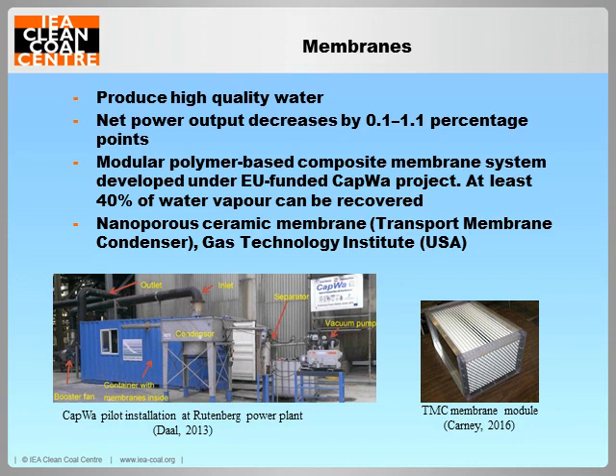The Gas Technology Institute in the USA is developing a nanoporous ceramic membrane called the transport membrane condenser. It is based on commercial technology that was developed for industrial gas-fired boilers. A two-stage system is being developed for coal-fired power plants that uses two separate cooling water streams to maximise recovery of both the water and latent heat in the flue gas.